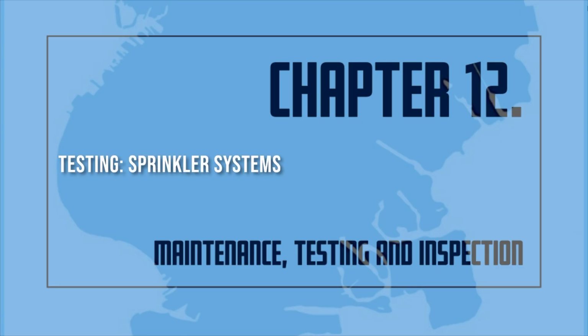2. Testing. A. Sprinkler systems. Alarm devices. Water flow alarms on wet pipe systems shall be tested quarterly. Vane-type water flow devices shall be tested semi-annually. Water flow alarms on wet pipe systems shall be tested by opening the inspector's test connection. If freezing weather conditions or other conditions disallow the use of the test connection, the bypass connection shall be permitted to test.